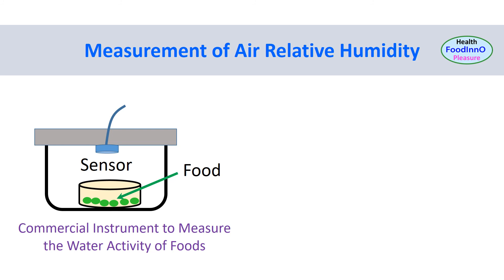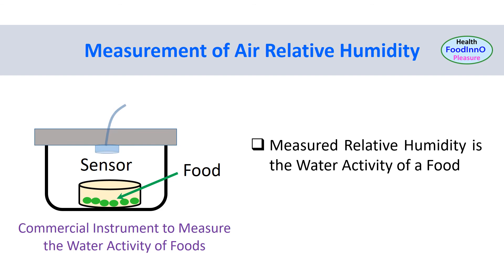Sample size also needs to be adequate so that moisture loss can be considered minimal. In this instrument, we are not equilibrating a sample at any specific relative humidity — we simply equilibrate with the air in the chamber and measure relative humidity by a sensor. We can easily measure the equilibrium air humidity, and it represents the water activity of the sample.